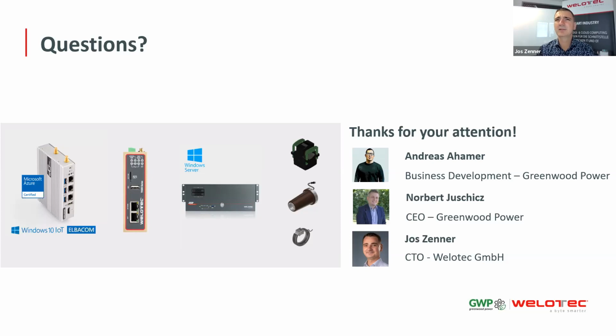So the first one: do we do MQTT—yes, we do MQTT, and we can do IEC 104 and MQTT at the same time. With MQTT you can also control secondary substations. It would perfectly work—you would move your intelligence from a traditional SCADA into a cloud system, or your traditional SCADA system could also directly support MQTT. At the end, MQTT is very similar to IEC 104, at least in basic functionality. They're both northbound protocols.